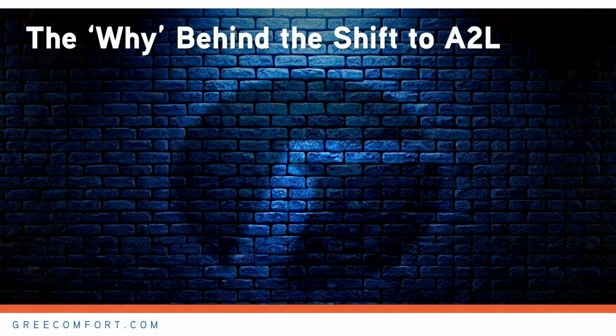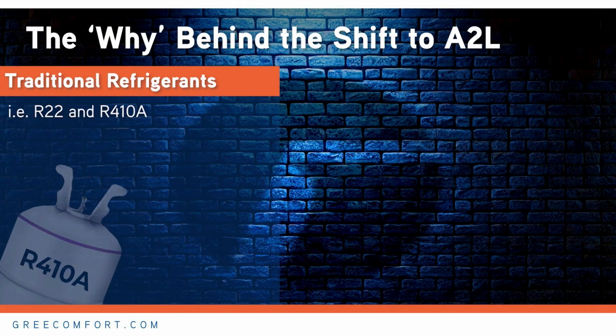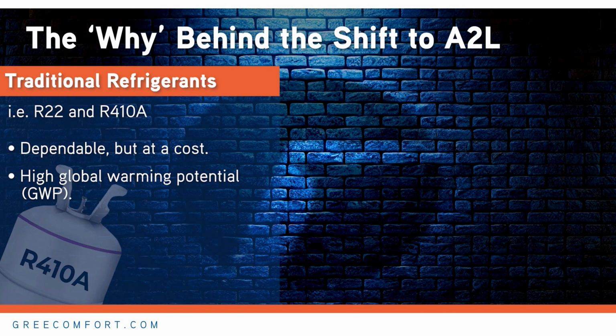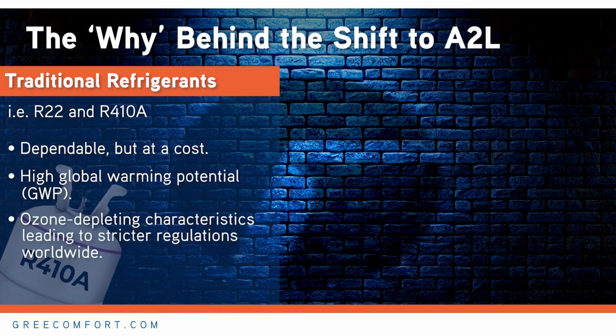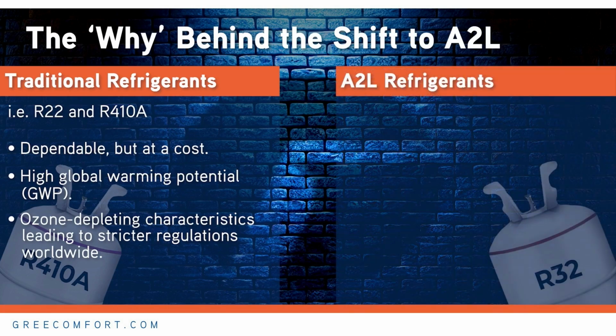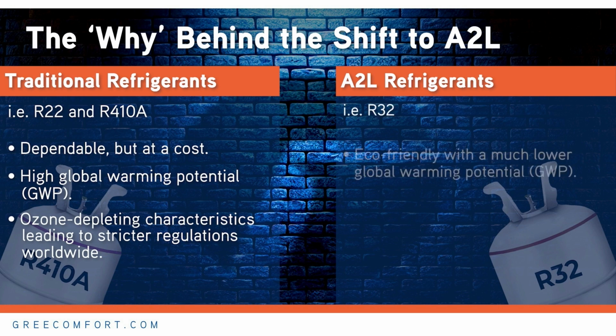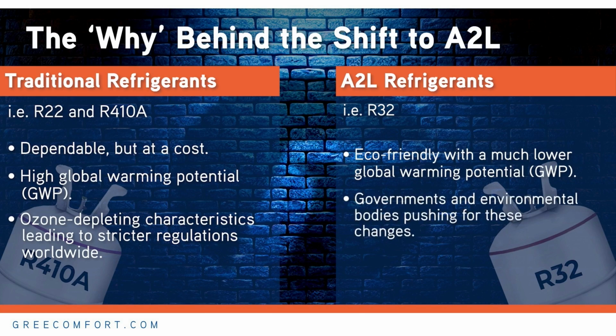Why the shift? For decades, traditional refrigerants like R22 and R410A have been industry standards. They've done the job well, but they come with a hefty environmental cost: high global warming potential, or GWP, and ozone-depleting characteristics have led to stricter regulations worldwide. That's where A2L refrigerants come in. These new refrigerants, like R32, are designed to be more eco-friendly, with much lower GWP. Governments and environmental bodies are pushing for these changes, and that means the entire HVAC industry must adapt.